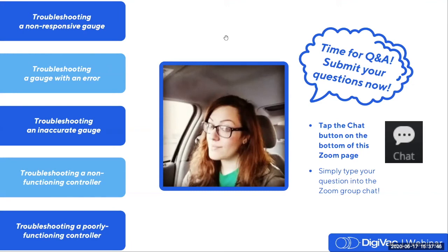Alternately, another problem that we've sometimes experienced with this thermocouple type sensor is you may get a resistance that's so high that while the sensor may technically be electrically connected, it's not going to read vacuum because the resistance of that one filament in particular is just so high. Attempting to excite that filament with the circuitry of our gauge isn't going to get a proportionate response. So I'd like to say thank you for that. That's a great observation, and I hope we were able to clear it up a little bit.